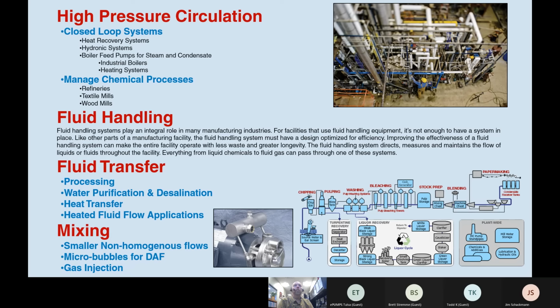So Regen turbine pumps are basically good for anything that uses high pressure circulation. Any closed loop system can use a Regen turbine pump. That includes heat recovery systems, hydronic systems, and boiler feed pumps for steam or condensate, including industrial boilers and heating systems. We do pretty well with chemical processes, including refineries, textile mills, and wood mills.